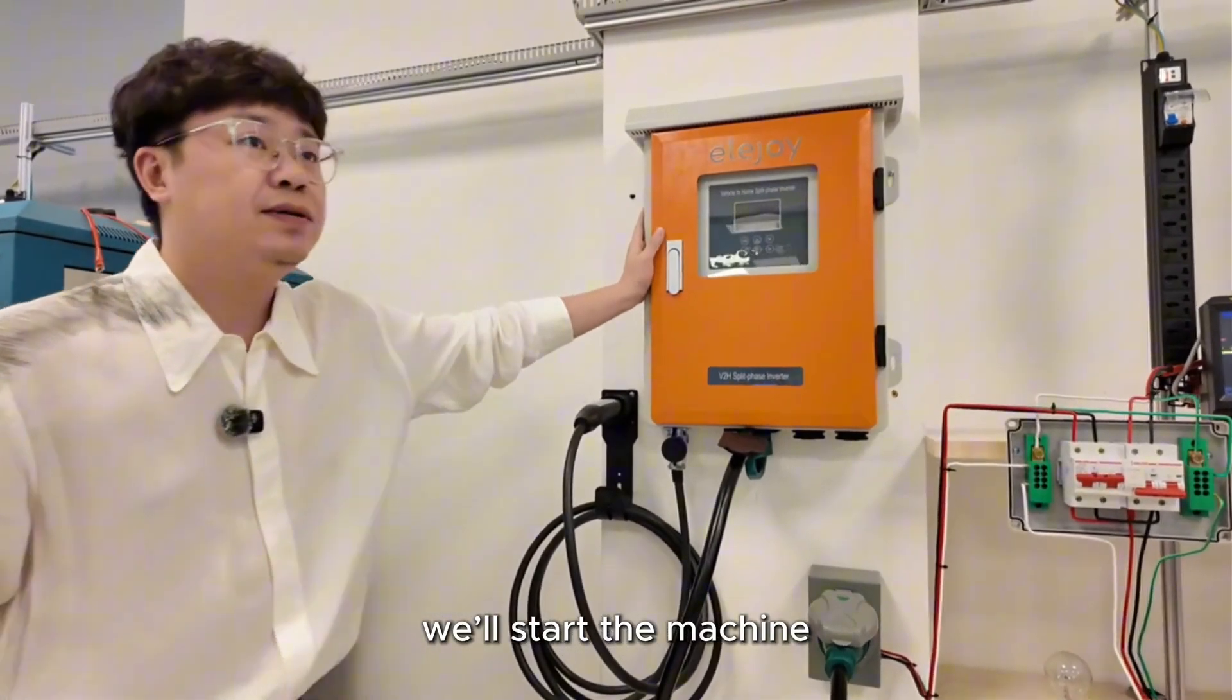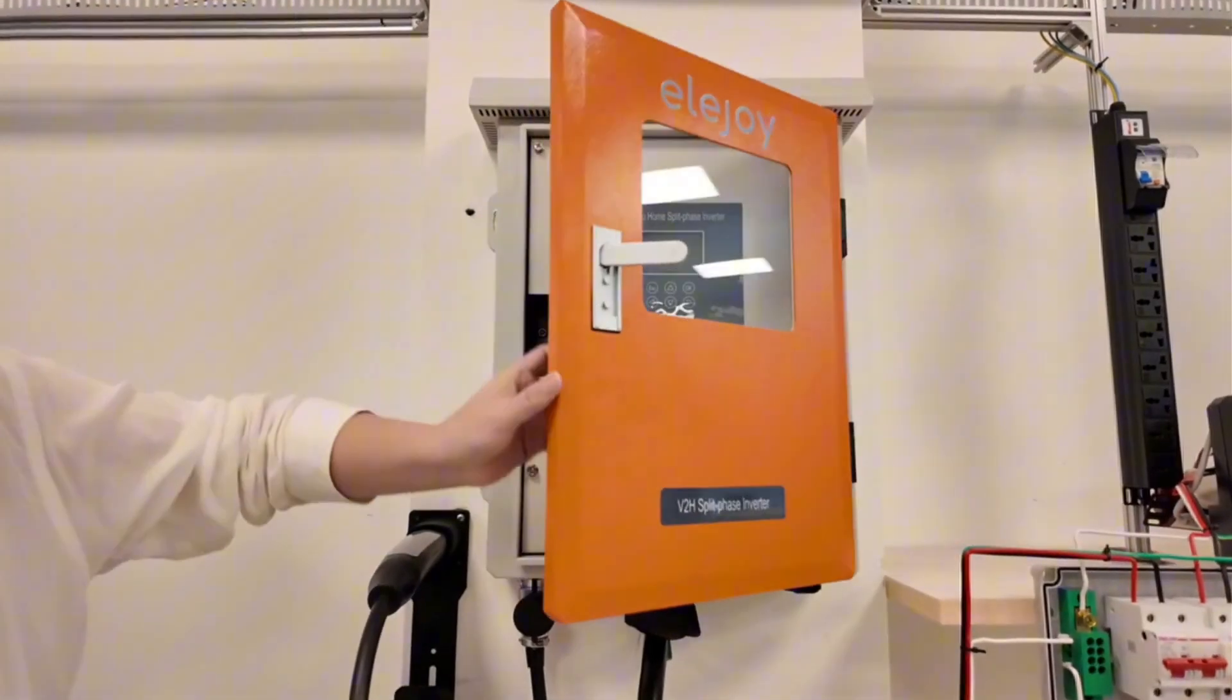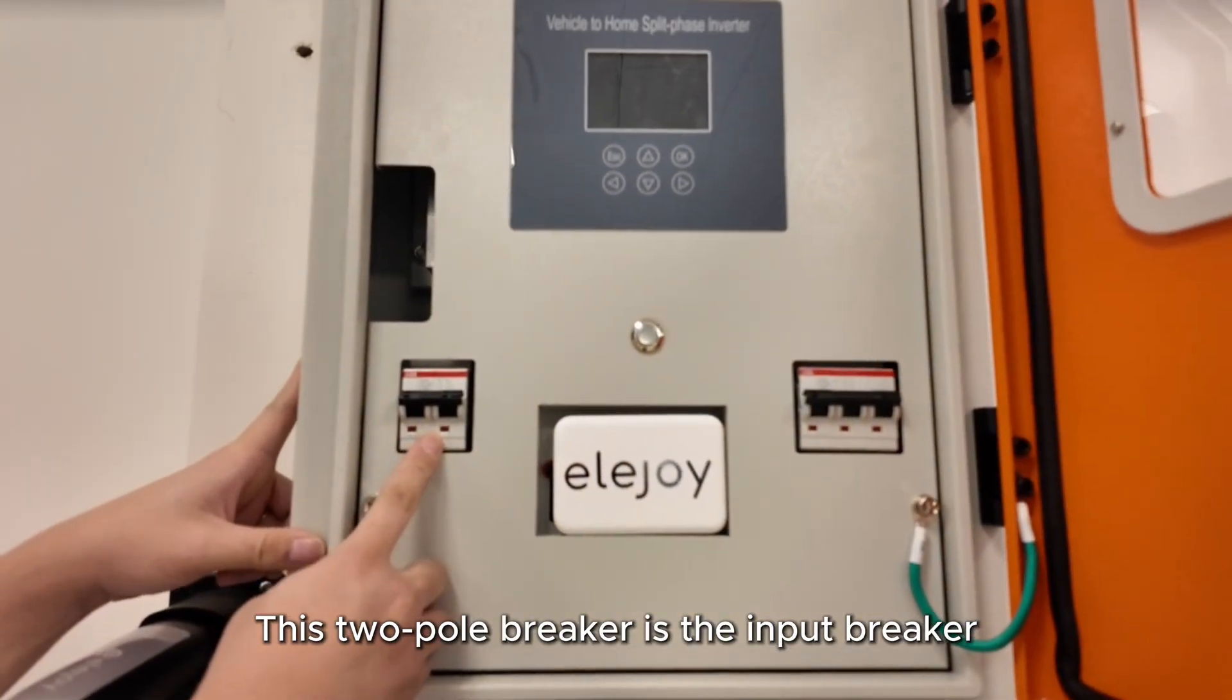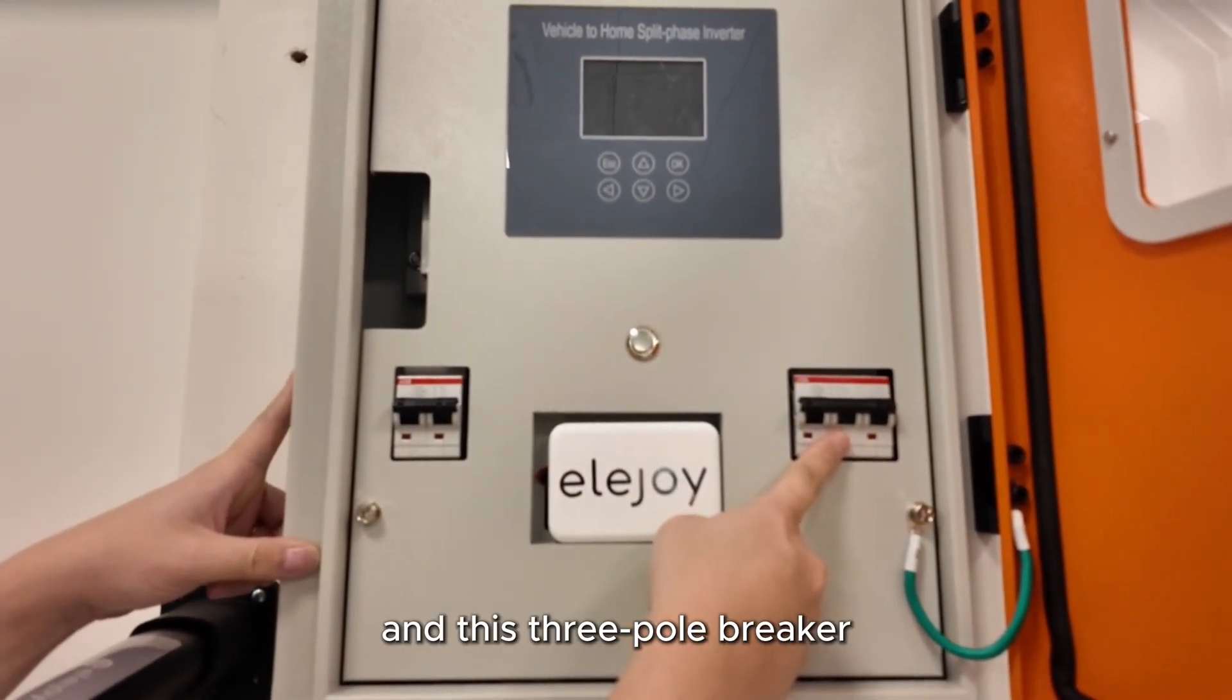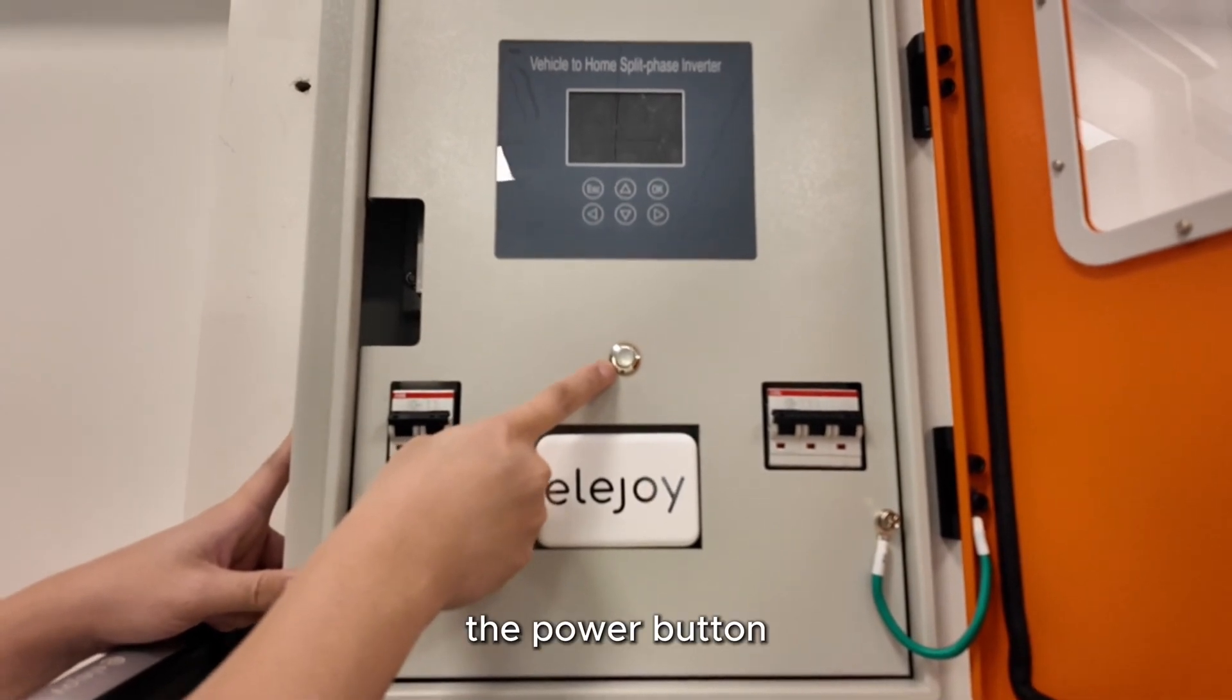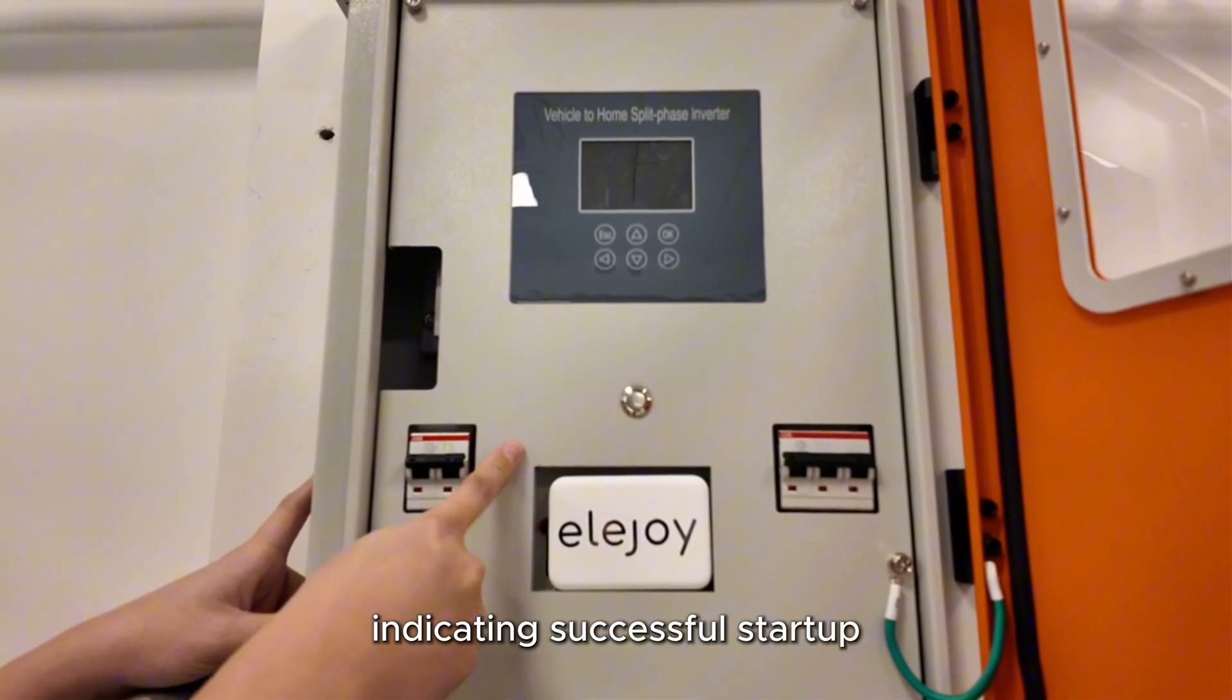Next, we'll start the machine. First, open the compartment door. Inside we'll see two circuit breakers. This two pole breaker is the input breaker and this three pole breaker is the output breaker. Then here is the power button. We press the power button. You'll hear a sound indicating successful startup.